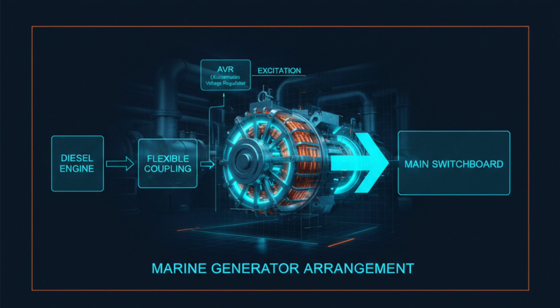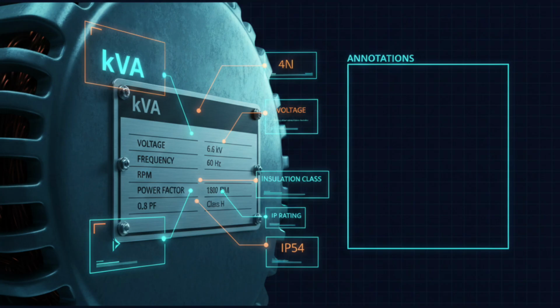An automatic voltage regulator continuously monitors terminal voltage and adjusts the rotor field current to maintain stable output during sudden load changes such as starting large motors or bow thrusters. In modern ships, this entire arrangement is integrated into the power management system, which handles starting, stopping, and load sharing between multiple generator sets.